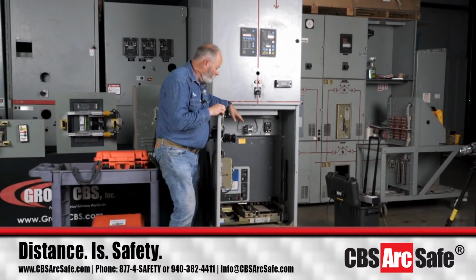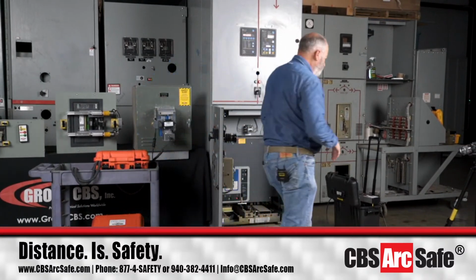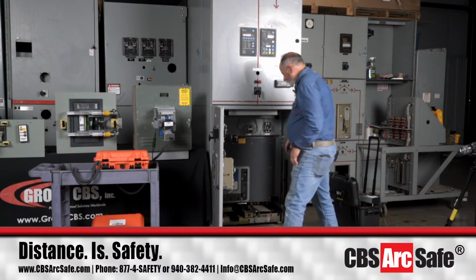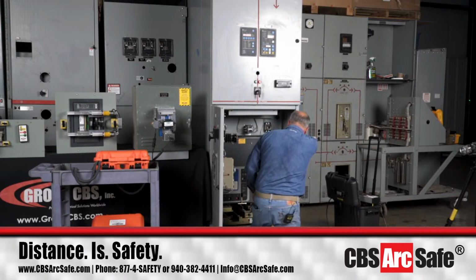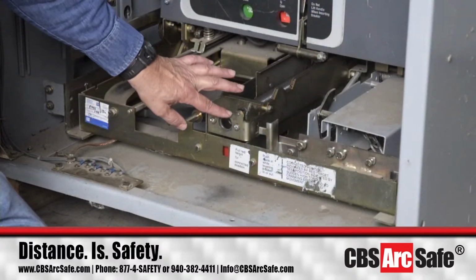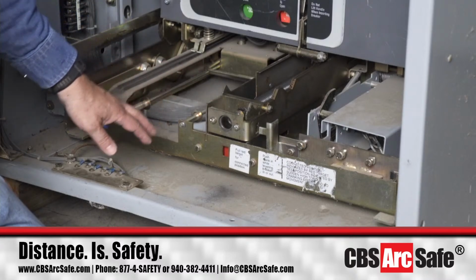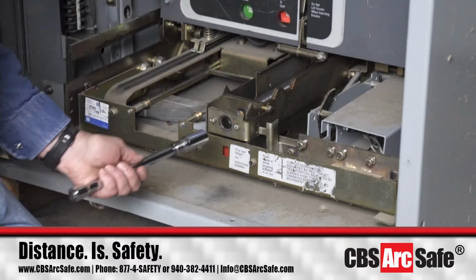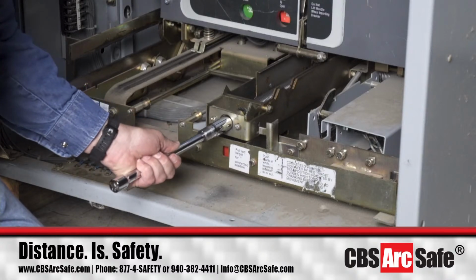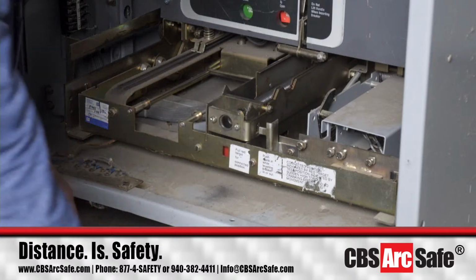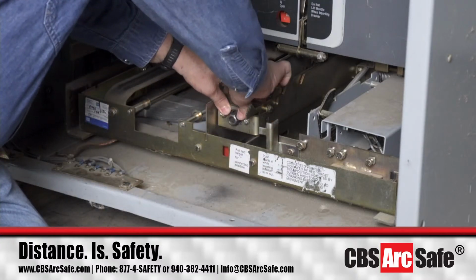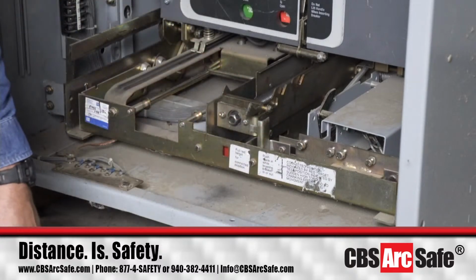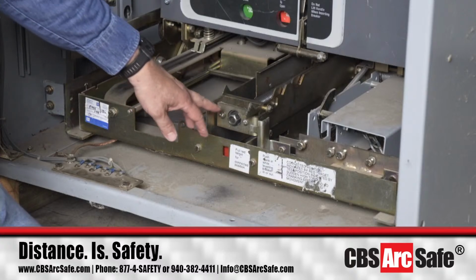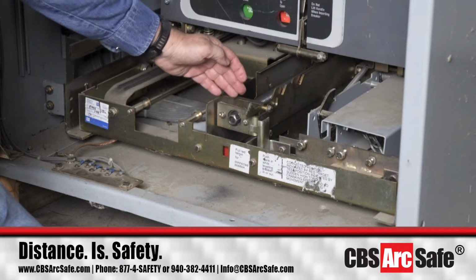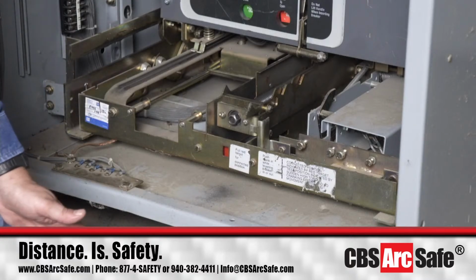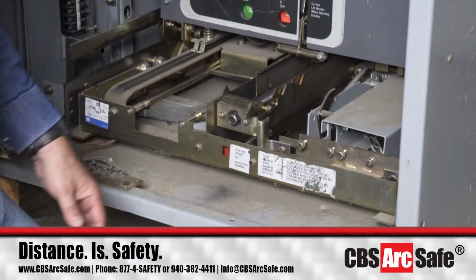Now, the basic racking mechanism of the VCPW hasn't changed in 33 years. I'm going to sit down here; we'll cut to a different camera so you can see what I'm doing. This is the lockout tagout interlock defeat right here. If I was trying to do this with an RS1, I have a problem because I'm trying to constantly push on this thing while getting the tool on at the same time. But whether I'm using the RS3 or the RS1, I push this in and move the lockout tagout interlock into place, it easily exposes the racking mechanism, defeats the spring, and now I have a much easier time, whether I'm dealing with an RS1 or an RS3 system, putting this on the breaker.